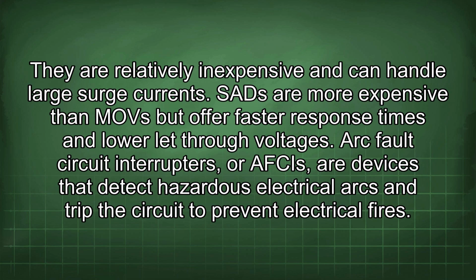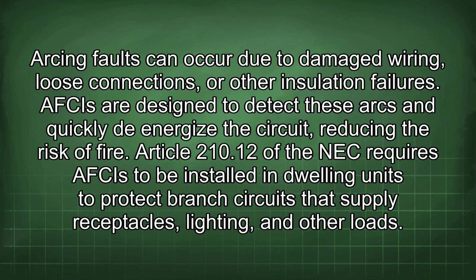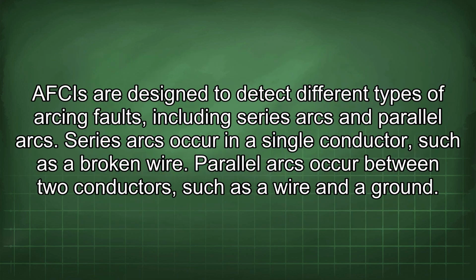Arc fault circuit interrupters, or AFCIs, are devices that detect hazardous electrical arcs and trip the circuit to prevent electrical fires. Arcing faults can occur due to damaged wiring, loose connections, or other insulation failures. AFCIs are designed to detect these arcs and quickly de-energize the circuit, reducing the risk of fire. Article 210.12 of the NEC requires AFCIs to be installed in dwelling units to protect branch circuits that supply receptacles, lighting, and other loads. AFCIs are designed to detect different types of arcing faults, including series arcs and parallel arcs.